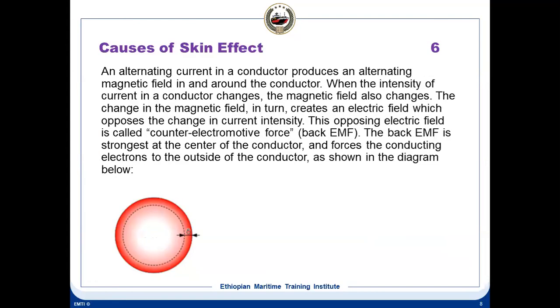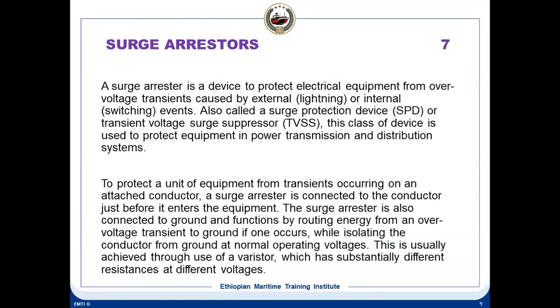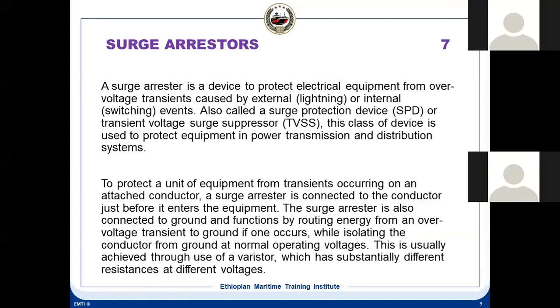And another one is the surge arresters. Basically, a surge arrester is like a varistor. We use varistors, like in generators and all, only to protect against surges. Surges means transient voltages, sudden peaks in the voltage. Suddenly the voltage just shoots up. When the voltage goes up and down a little bit all of a sudden, those are called transients.